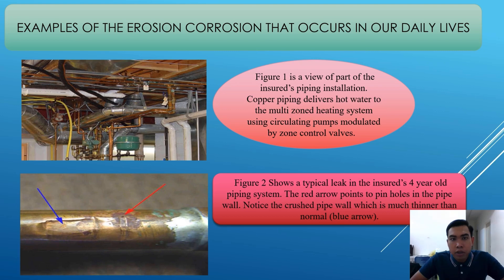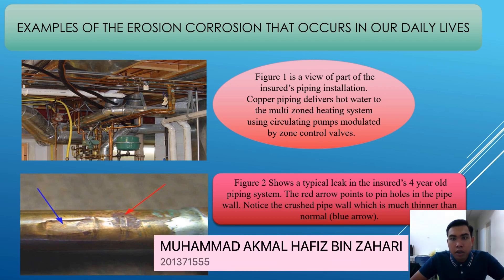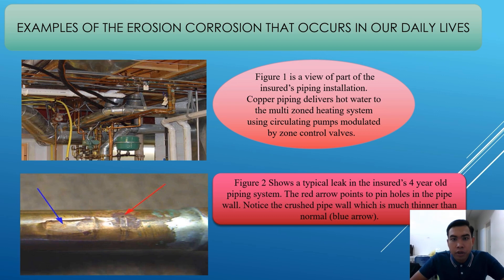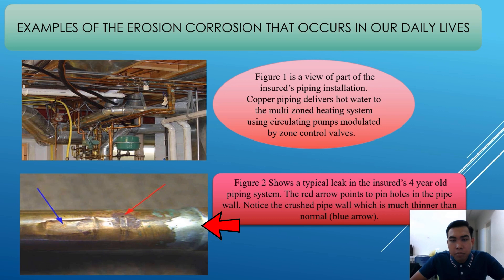For examples of erosion corrosion that occur in daily life: number one shows a view of part of the insured's piping installation, using copper piping in a multi-zone heating system with pumps moderated by zone control valves. Figure 2 shows a typical leak for an old piping system. The red arrow points to a pinhole in the pipe wall. Notice the crushed pipe wall, which is much thinner than normal.